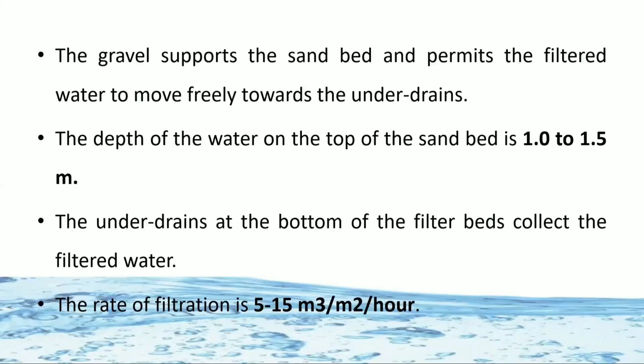So the gravel supports the sand bed and permits the filtered water to move freely towards the under drains, and also stops the backflow of the water. The depth of the water on the top of the sand bed is 1 to 1.5 meter. Here the rate of filtration is 5 to 15 m³ per meter square per hour.